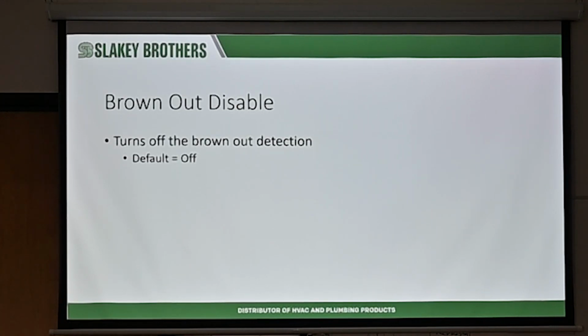Brownout, it comes default off, you can leave it like that. Brownout is, if you ever drop below 187 volts, the equipment is not designed to work there. Your unit just won't work. And that's what a brownout is. So a brownout could be faulty electrical from the street, it could be a faulty house breaker, whatever causes a voltage to drop down below 187, that's a brownout. It's just a fault that tells you there's an electrical problem. It comes defaulted off. If you're out in the country, in the sticks, somewhere where maybe there are problems, you might want to enable it just so the homeowner knows that there's electrical issues. Otherwise, you can leave it off.